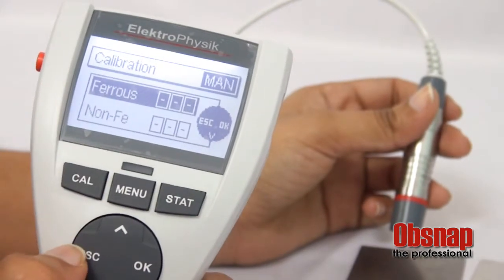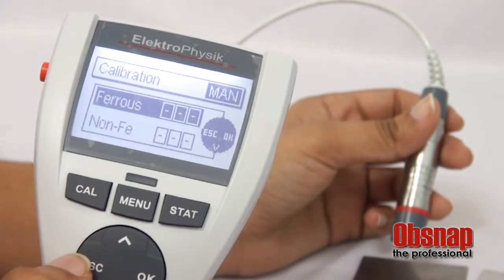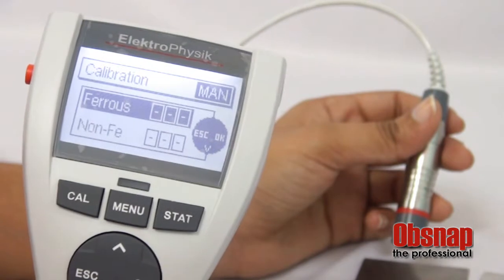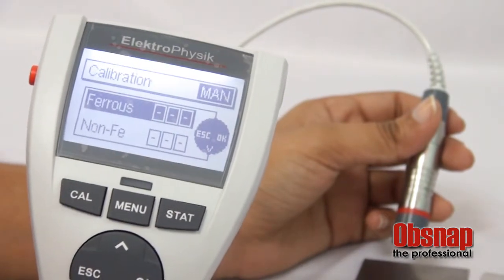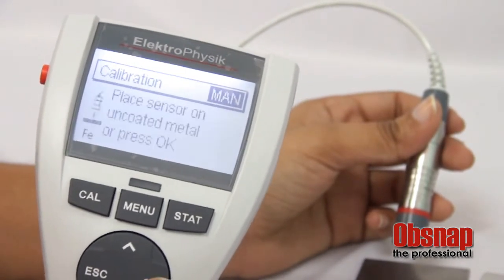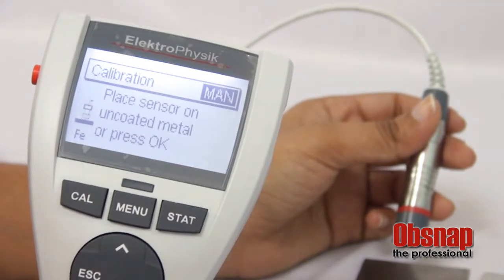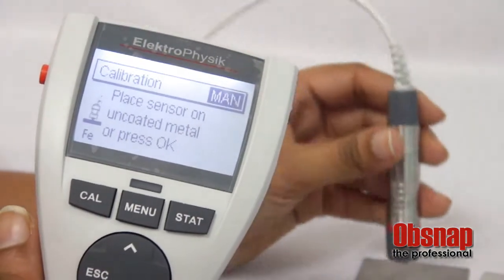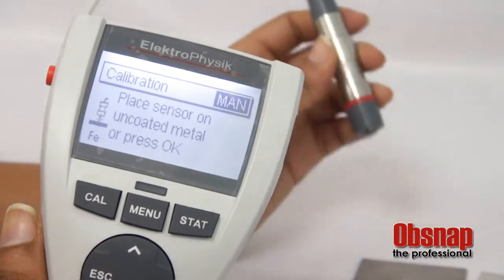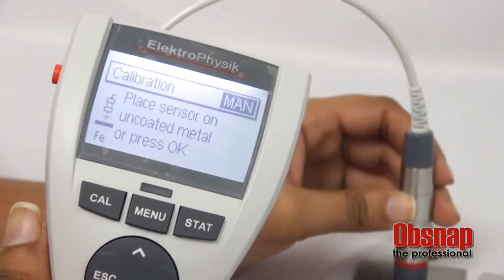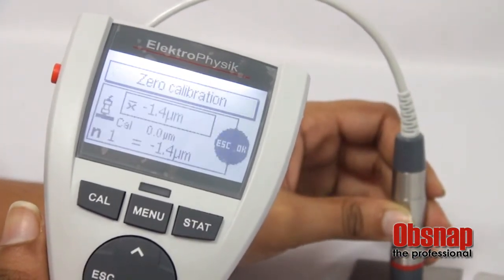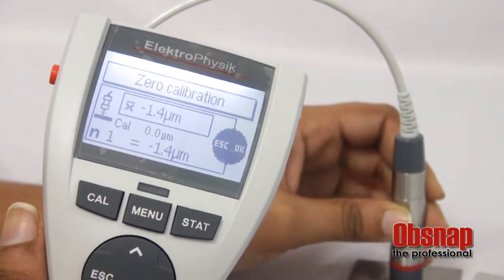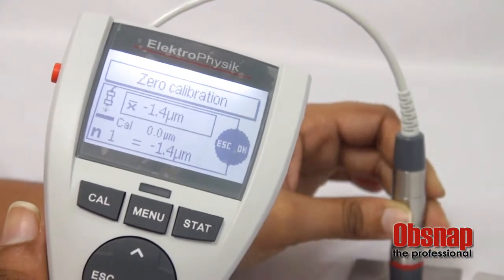It will display ferrous and non-ferrous. First, you can choose ferrous to perform your calibration. On ferrous, click OK button, and then it will display, put the sensor on uncoated metal. So put the sensor probe on the plate, 0 plate, and then take the measurement. This one is 1 point calibration.